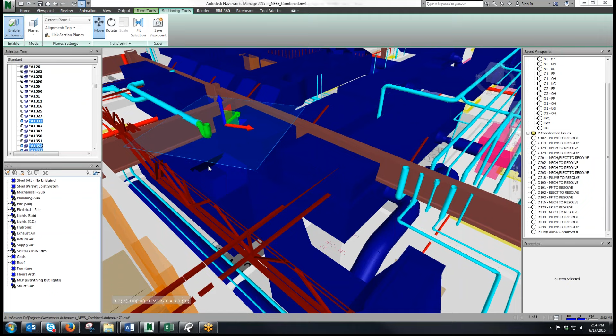Adam, would this be an option, just eliminating this drain completely right where it's at, possibly sleeve the slab and take the condensate down? This is probably going to be, at the largest, a 1 inch, possibly a 3/4 inch drain line. Run it to wherever we can, on down below the first floor.